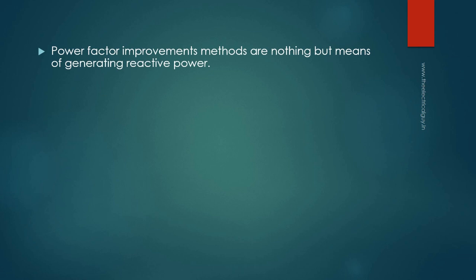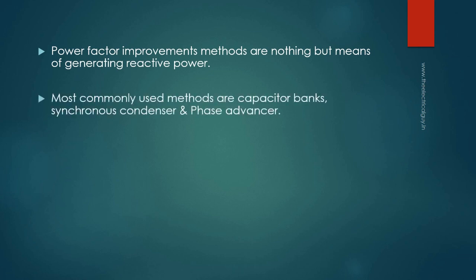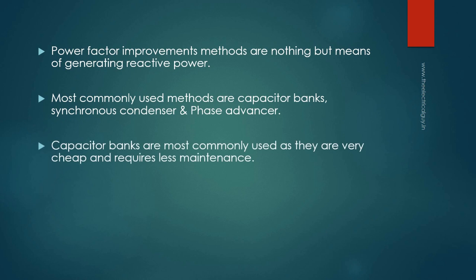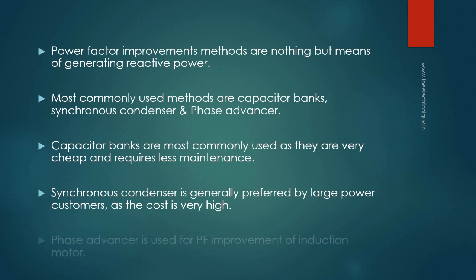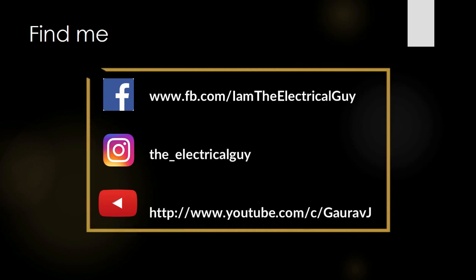To summarize: power factor improvement methods are nothing but the means of generating reactive power. The three most commonly used methods are capacitor banks, synchronous condensers, and phase advancers. Capacitor banks are most commonly used as they are cheap and require less maintenance. Synchronous condensers are generally preferred by large power customers due to their high cost. Phase advancers are used for power factor improvement of induction motors.